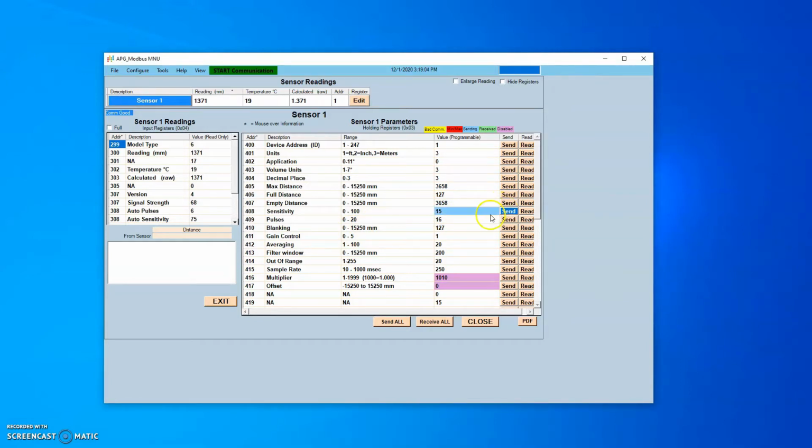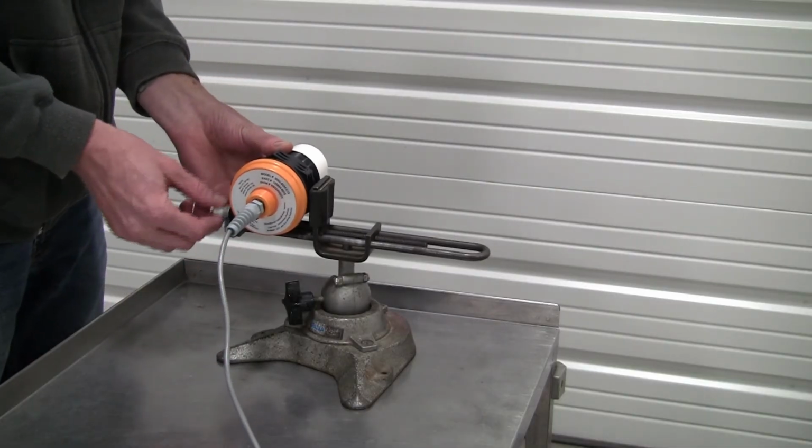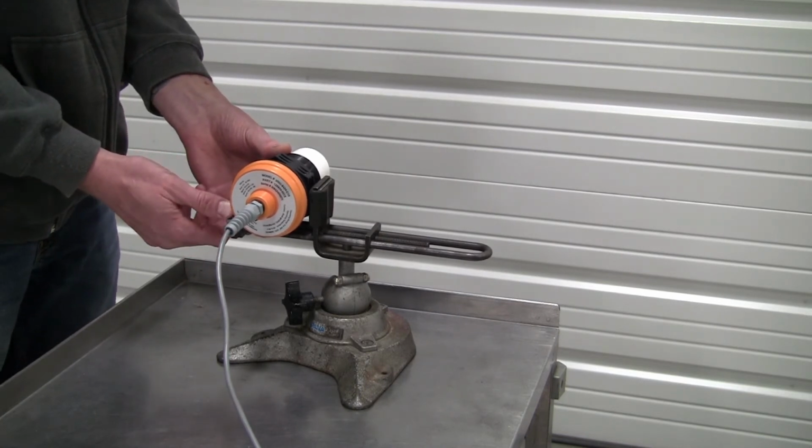In particularly difficult installations, setup problems may lead to questions of the transducer's functionality. The following test procedures may be used to verify that your ultrasonic sensor is operating correctly, helping you remove one variable from your troubleshooting list. These tests involve removing the sensors from their installation for verification in a controlled environment with a known good target.